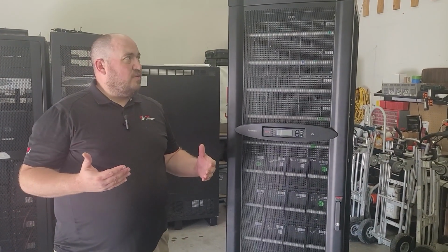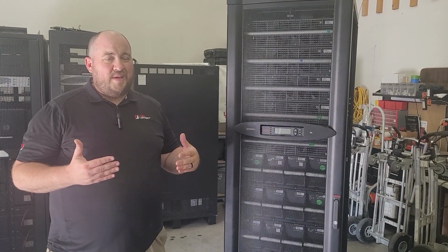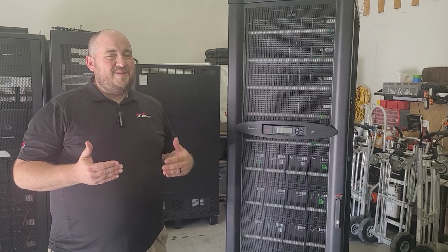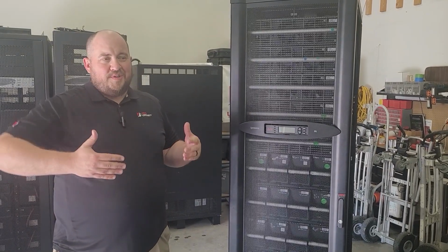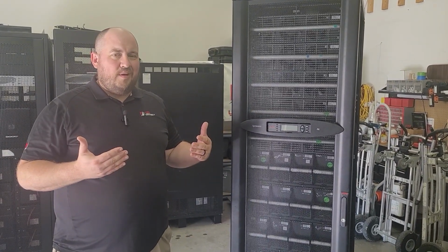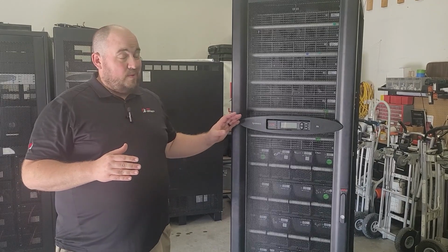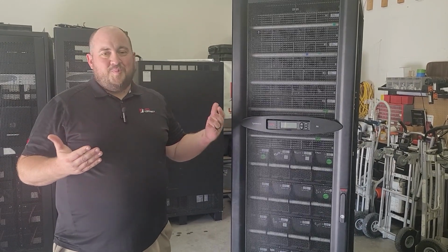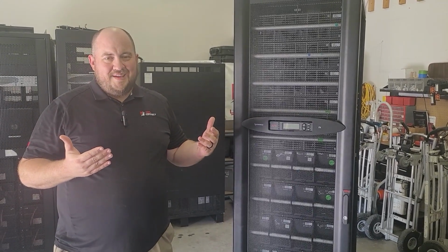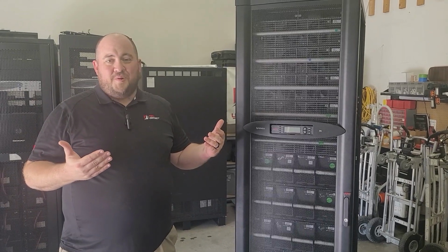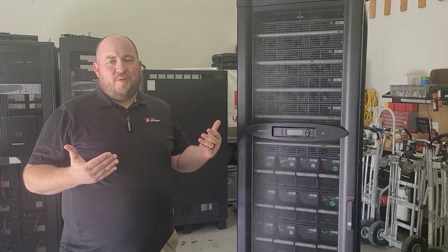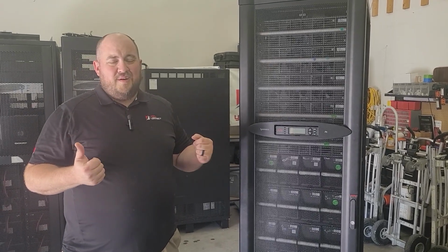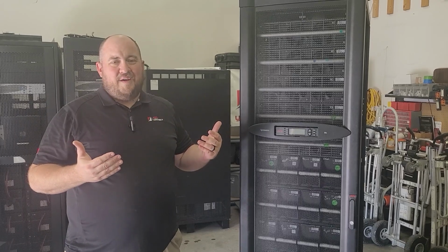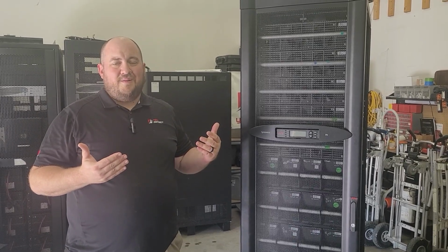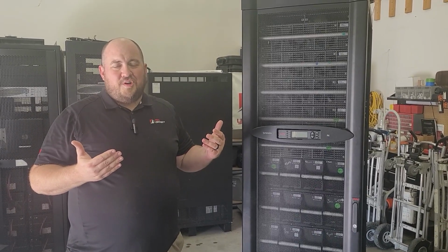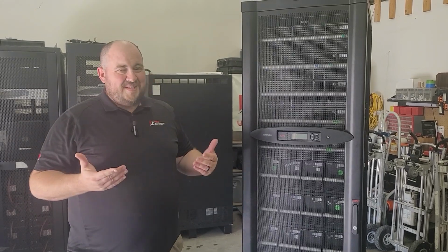As a manufacturer, APC is not great to work with as a third party. A lot of the times they don't want to give us the support that we need to be able to change things out. Recently they had a recall on some breakers on the PDUs that go with these systems. We had a customer who ran into that issue, and we ended up having to call the factory. They wouldn't allow us to change that out for them. During that time, if it's on a system like that, it can be after hours - an expensive call out, expensive after hours charge and work to be done. Just something we don't like.